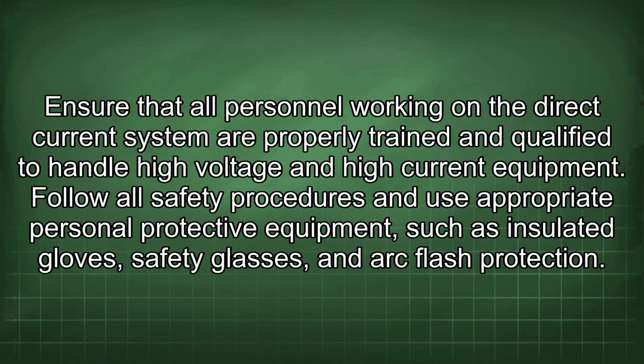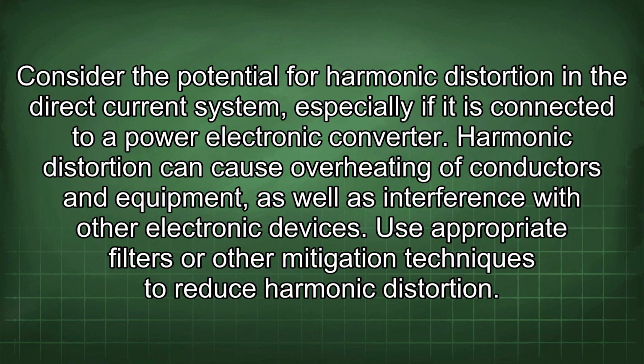Ensure that all personnel working on the direct current system are properly trained and qualified to handle high voltage and high current equipment. Follow all safety procedures and use appropriate personal protective equipment such as insulated gloves, safety glasses, and arc flash protection. Consider the potential for harmonic distortion in the direct current system, especially if it is connected to a power electronic converter. Harmonic distortion can cause overheating of conductors and equipment, as well as interference with other electronic devices. Use appropriate filters or other mitigation techniques to reduce harmonic distortion.